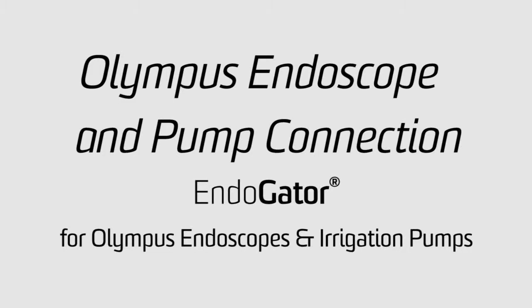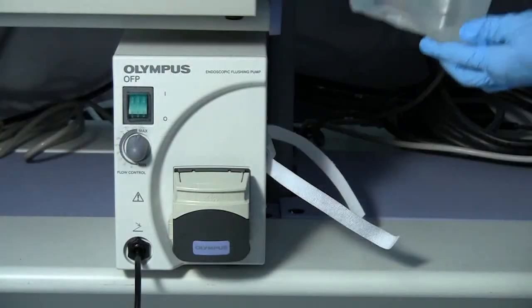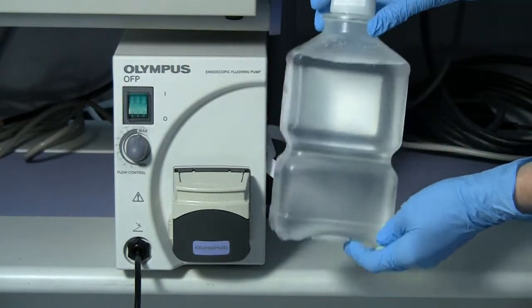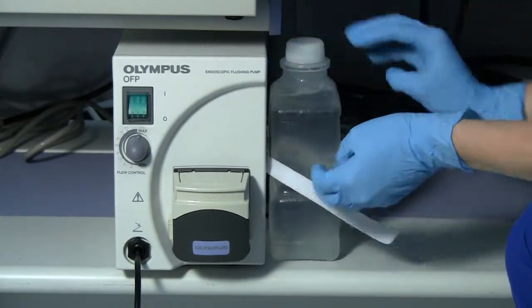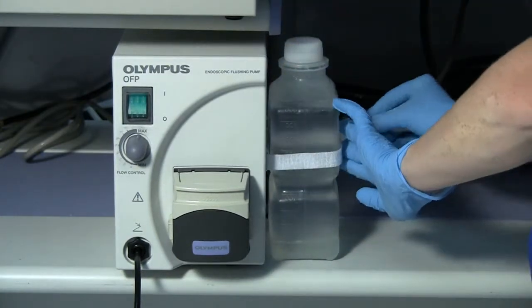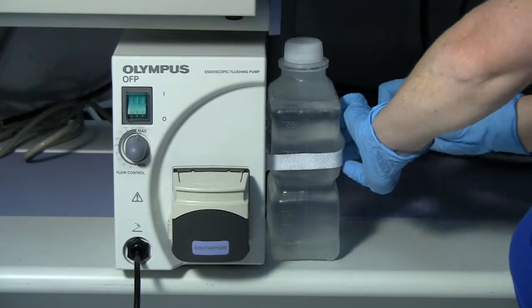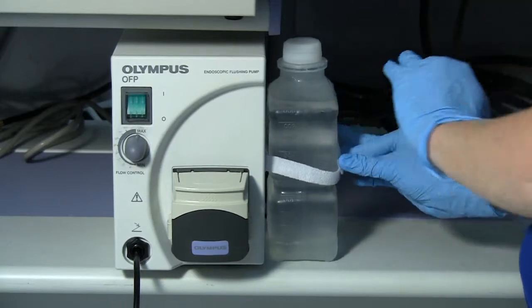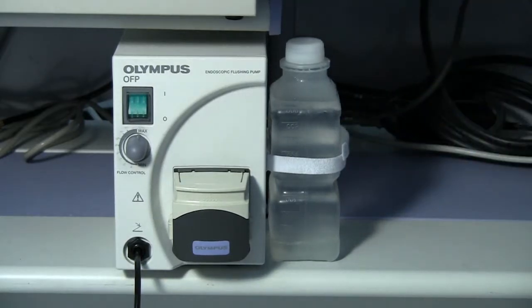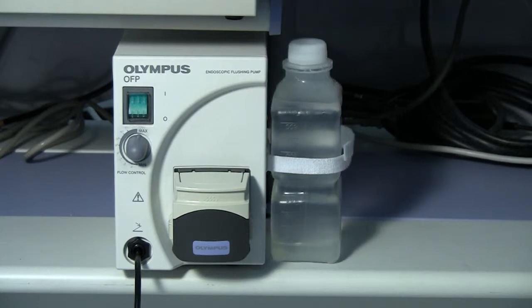All EndoGator technology is used in conjunction with the sterile water bottle. First, place a sterile water bottle as shown here next to the OFP pump. Removing the water bottle holder from the pump can sometimes make this process easier when using a non-cylindrical bottle like the one seen here. Attach the Velcro strap to the bottle to keep the bottle in place.